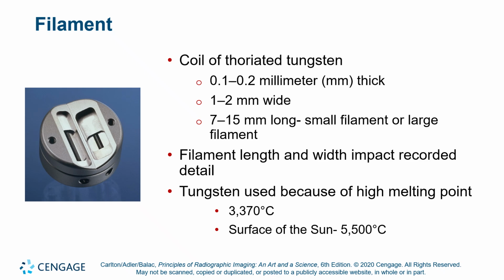Really, really hot. Okay. We want to heat the tungsten up. So just like at the blacksmith, when they heat up the iron or the steel, they put it in the forge, and the fire heats up the metal till it glows red, then it glows orange, then it glows yellow. Somewhere between orange and yellow, the metal starts to get soft like clay, and you can pound it into various shapes. In the same respect, tungsten, we don't heat it up because we want it to get soft necessarily. We heat it up because we want to excite the electrons on it. And so we heat it up to just below the melting point. It's glowing white hot, and lots of electrons are excited. Okay? And we'll use those excited orbital electrons to create the tube current.